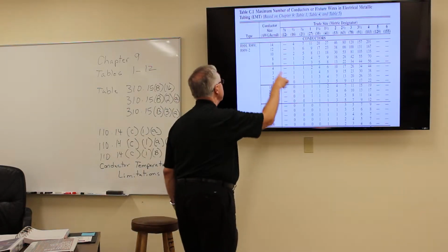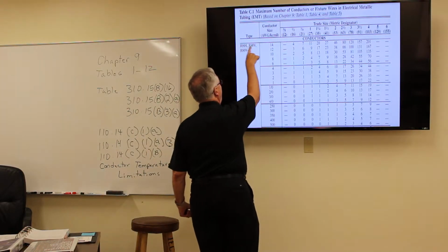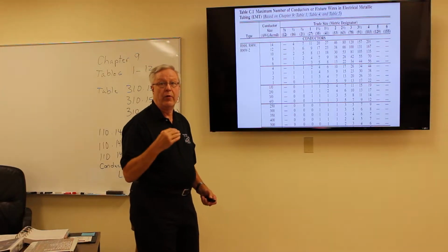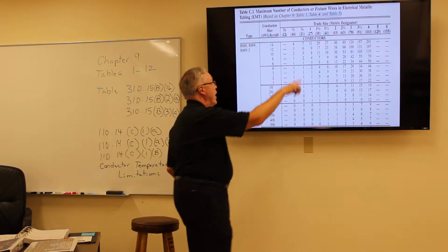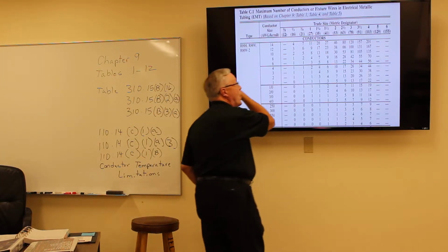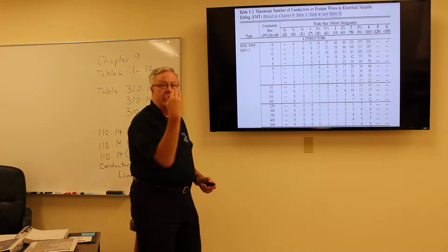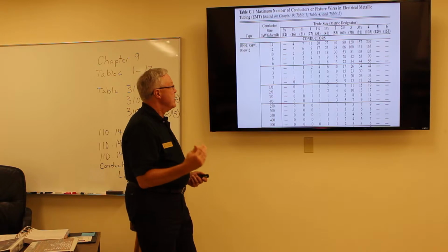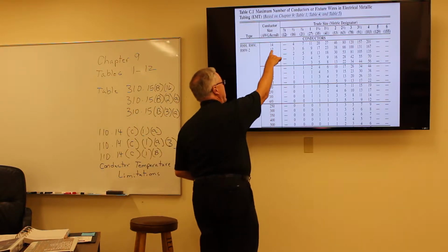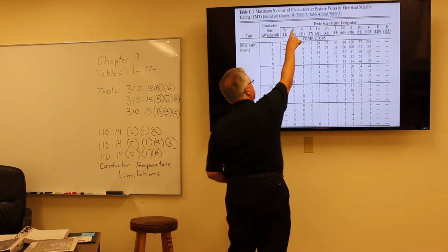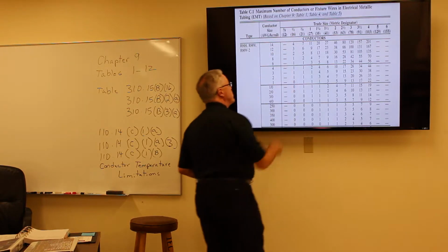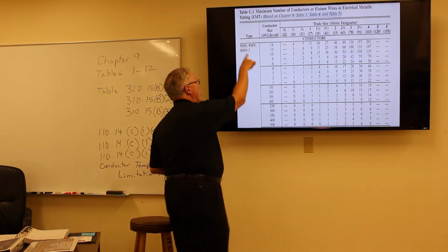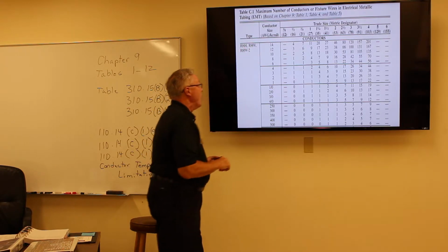Annex C also lists the maximum number of fixture wire permitted in each type of conduit. If you'll notice in C1, it goes through here. You'll always look and make sure that you know what type of conductor insulation is on the conduit, and also make sure you're using the correct type of raceway system. In this case, we're dealing with EMT, but there's flexible, there's rigid, IMC, and so forth. In here, if you go to number 12 conductors, you'll see a 1/2 inch conduit. You can install 3 number 12s in a 1/2 inch EMT conduit of type RHW and RHH.